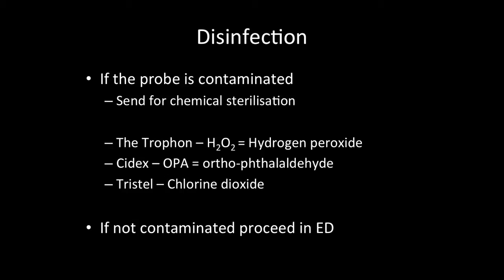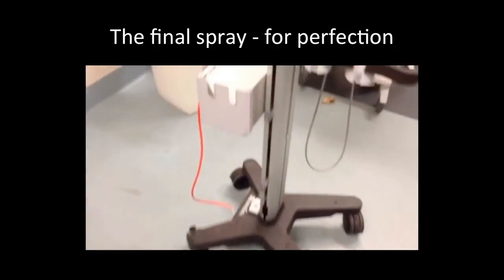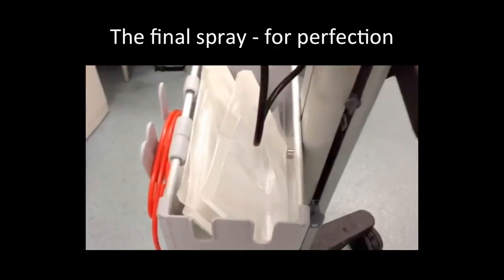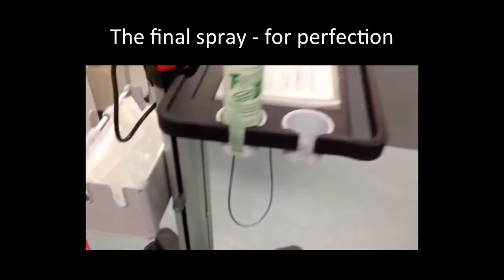Hopefully, if you use a probe cover, the probe won't be contaminated. And if it's not contaminated, washing it like that is fine. Obviously, this isn't true for transvaginal or transrectal ultrasound probes, but for ones used on the skin, that's fine. So once you've washed it, just to perfect our cleaning, there are the probes on the back.